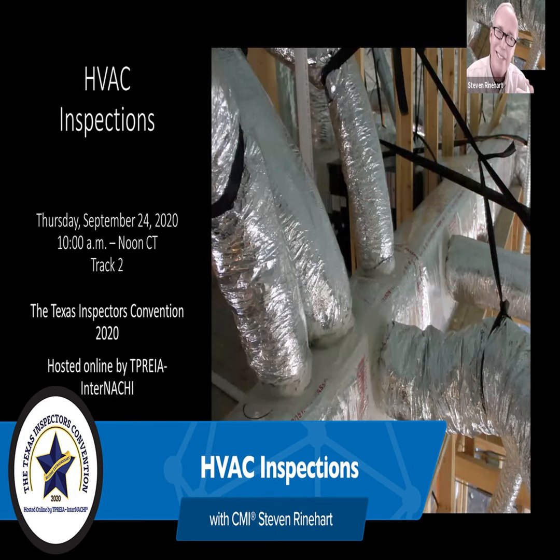Dirty coils. If you can see the coils and they got debris on them, I make a note of it. If it's really bad, I really make a note of it. In a lot of units, you can't. A gas unit, you can't see the coil. Only way you could see that is probably move the flue and try to open up the cover, and that's a bit beyond our license. I'm not going to do anything to move a flue. Disconnect the flue, take it apart, just to look at the coils.